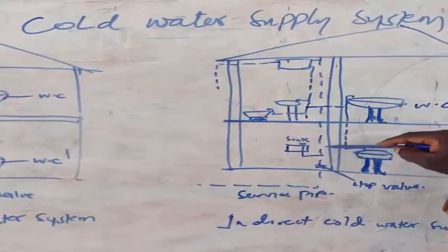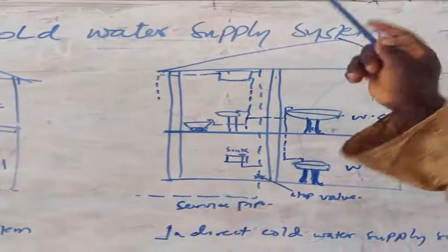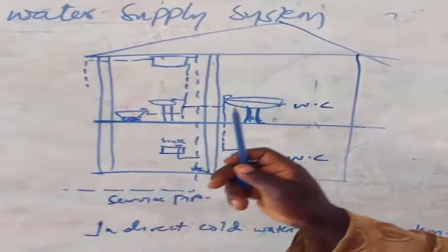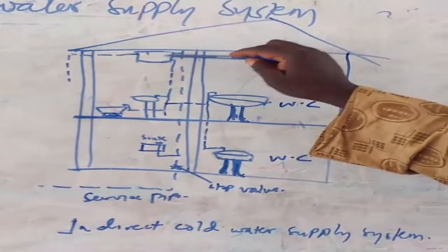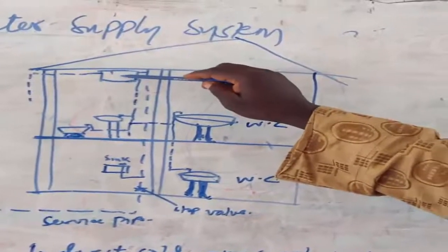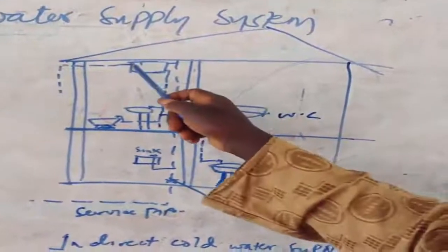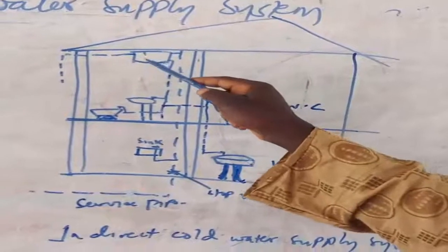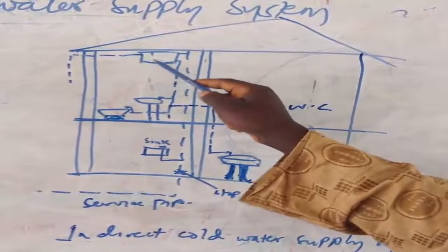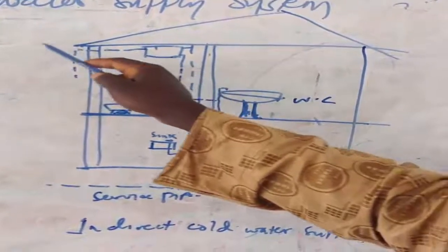The pipe here pushes the water through the pressure pipe. It goes here. It does not supply any other sanitary appliances. Rather, it comes here to feed into the system. It feeds into this system. And as it's feeding into the system, there is an overflow. As it is going here, if it fills the system, there is a warning pipe, or what is called an overflow pipe, that is telling you that the water has filled the tank.